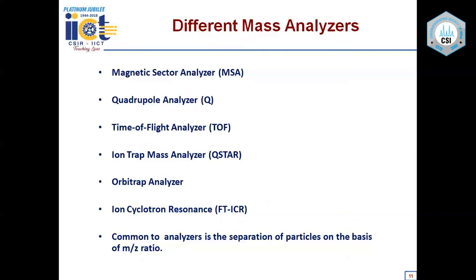There are different types of mass analyzers. In sector mass spectrometers, magnetic sector and electrostatic sector analyzers are used. In quadrupole mass spectrometers, a quadrupole analyzer is used. Time-of-flight mass spectrometers use a flight tube. Ion trap mass analyzers trap ions. The Orbitrap analyzer traps ions via an outer barrel electrode and a spindle electrode; ions in orbital motion produce image currents. Ion cyclotron resonance mass spectrometers are also available. Common to all analyzers is separation of particles on the basis of m/z ratio.